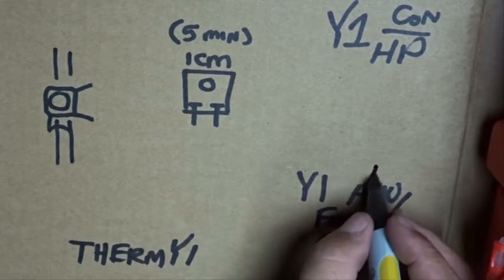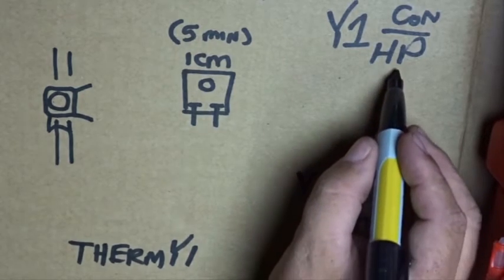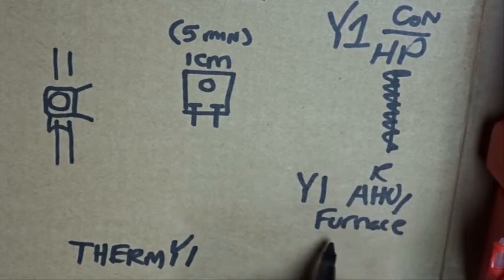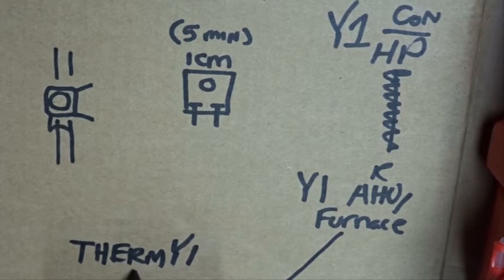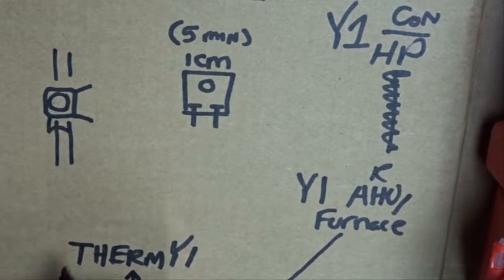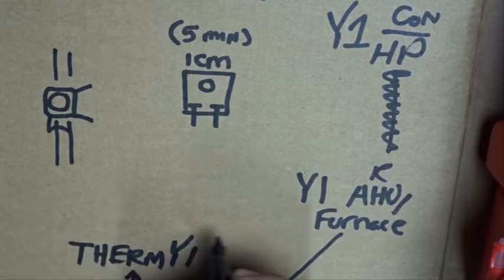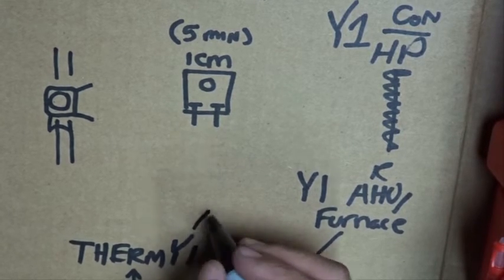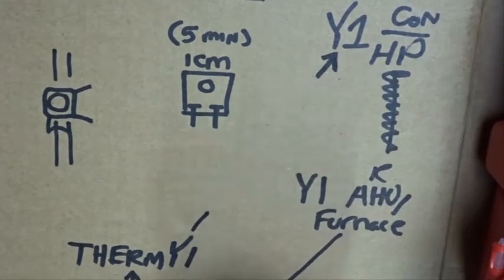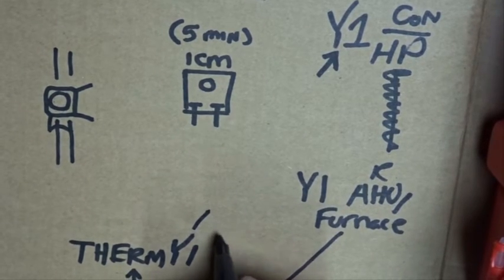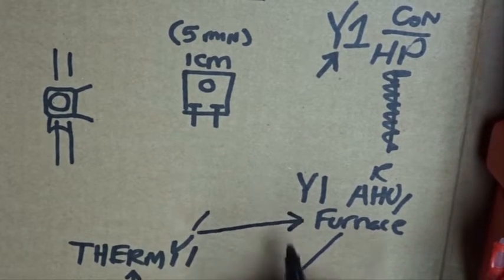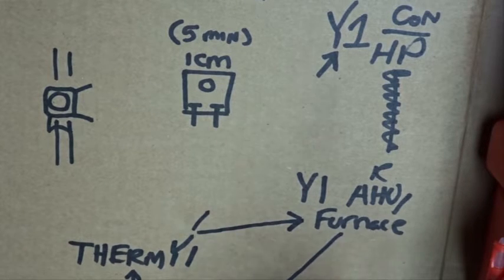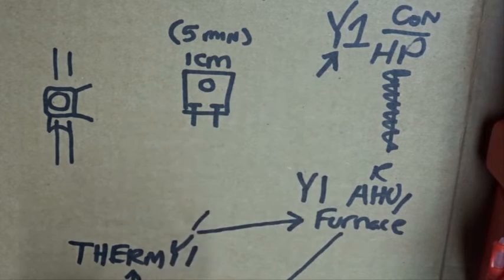You just want to separate that signal before it gets to the condenser. So your air handler, you have your R and it's sent to the thermostat to power the thermostat. And then when you hit the cooling and the cooling comes on, it's going to send a Y1 signal to your condenser, typically. And sometimes it's going to send a Y1 signal to the furnace as well. But we're not concerned with that. That's going to tell the ECM blower to run at a certain speed if you have that. PSC that's irrelevant.